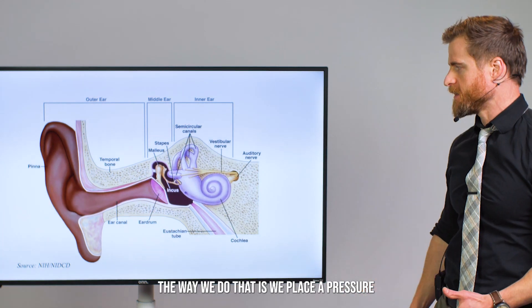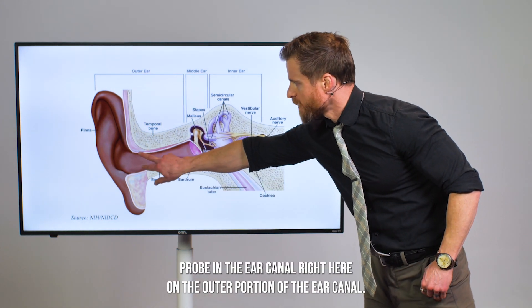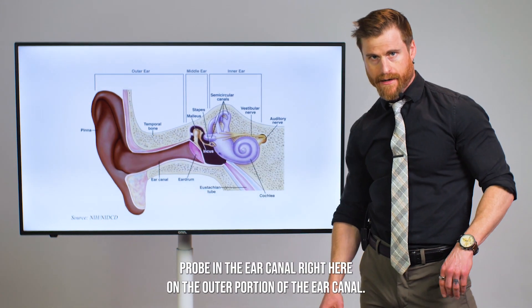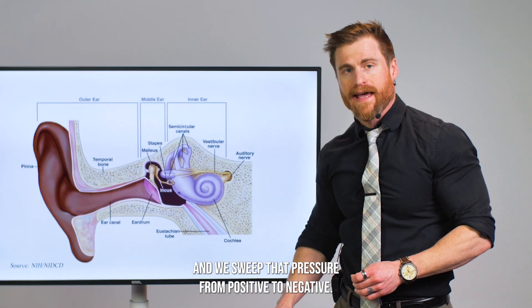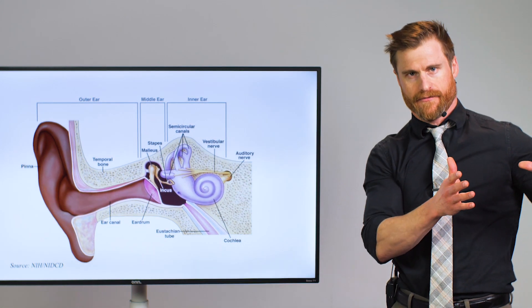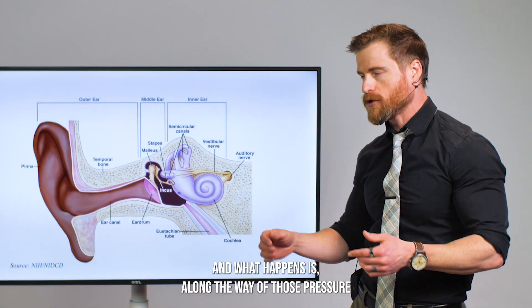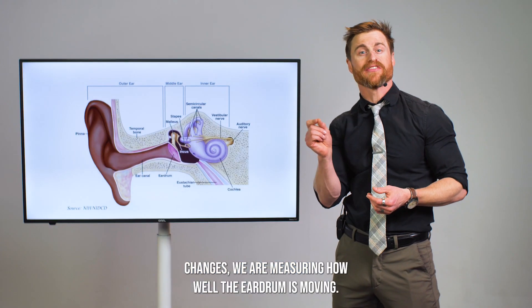The way we do that is we place a pressure probe in the ear canal right here on the outer portion of the ear canal. We create a seal, and then we apply some pressure in the ear canal and sweep that pressure from positive to negative. What happens is along the way of those pressure changes, we are measuring how well the eardrum is moving.